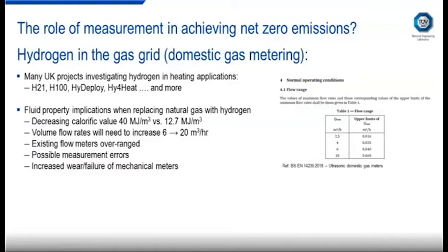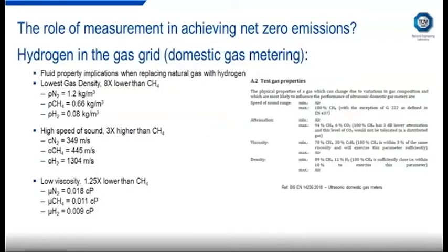And you can imagine that existing flow meters would become overranged. And with mechanical type flow meters, that could contribute to increased wear or premature failure of the meters. But at the very least, we'd expect to see increased measurement errors. There's other fluid properties that are important as well, such as gas density. This is 8 times lower for hydrogen compared to natural gas, and the speed of sound is 3 times higher. The viscosity is in a similar range. That's not quite so much of an issue.